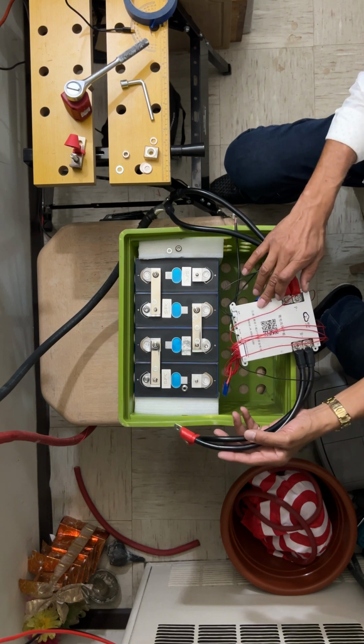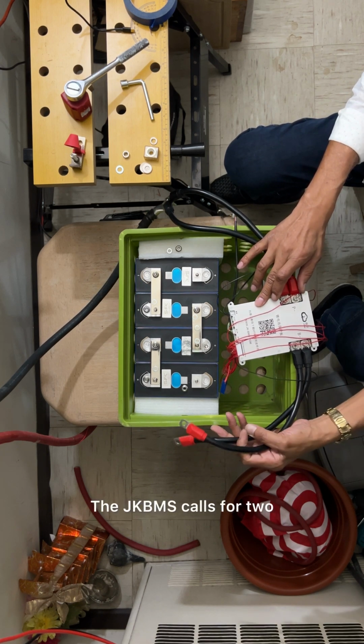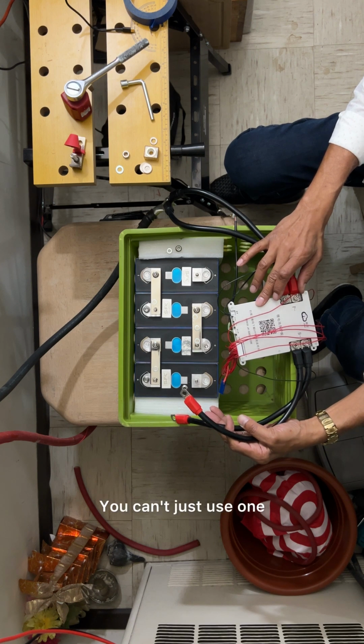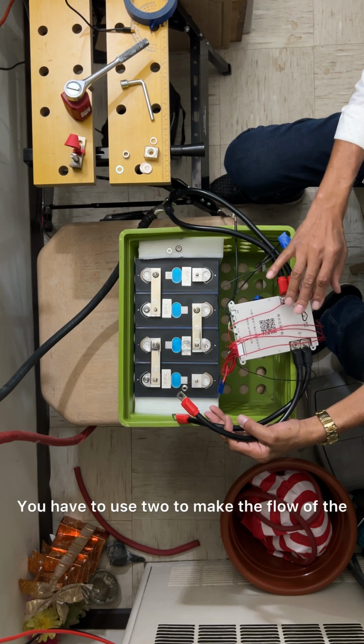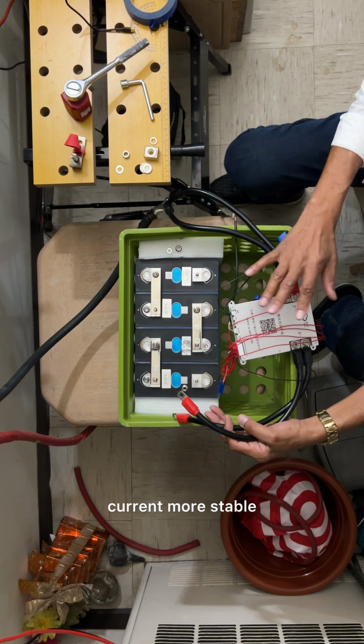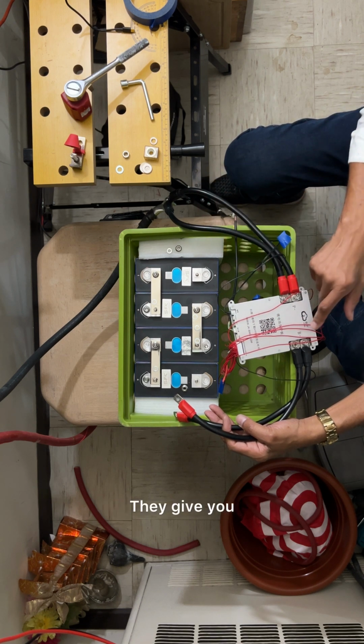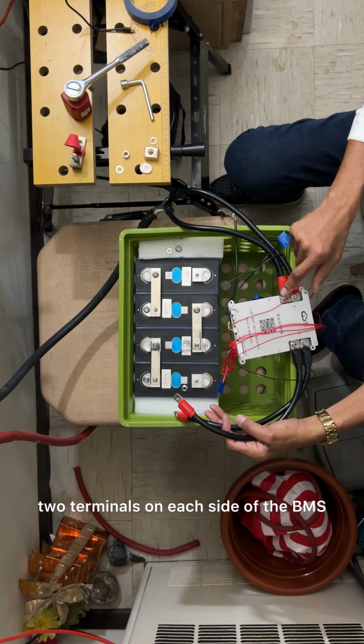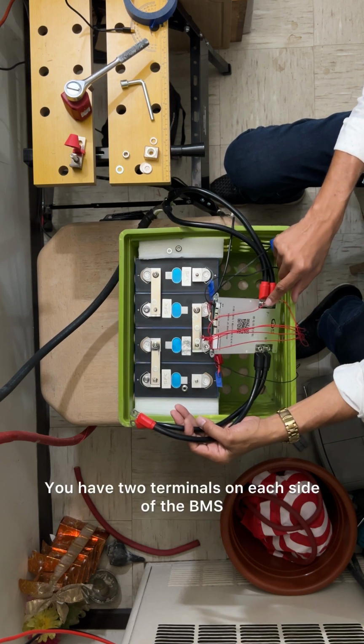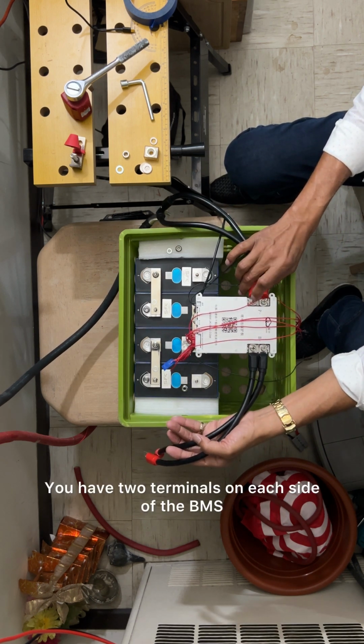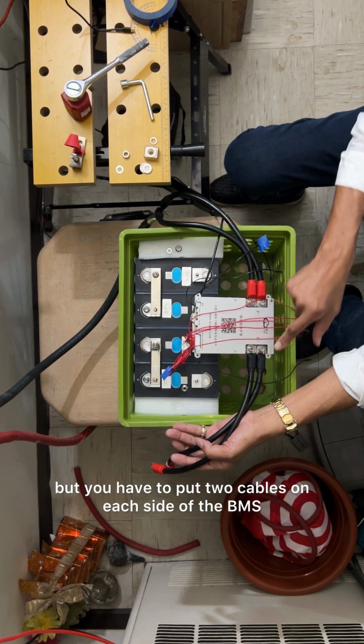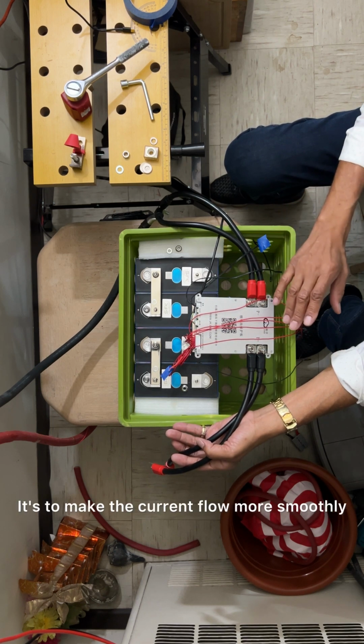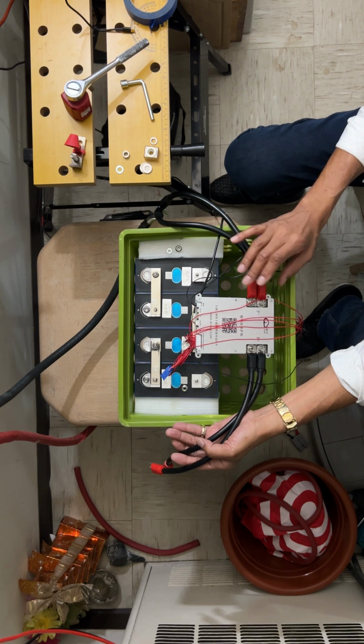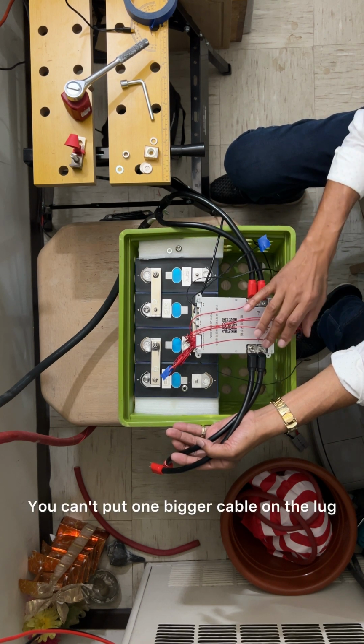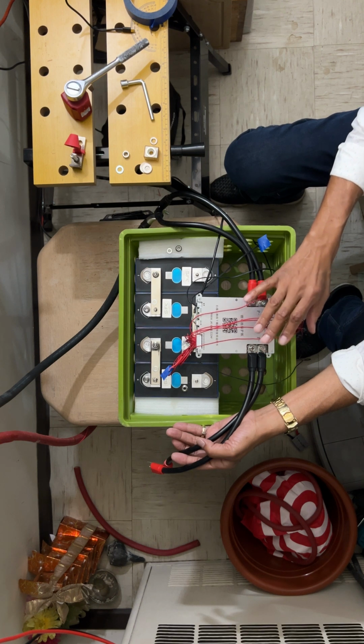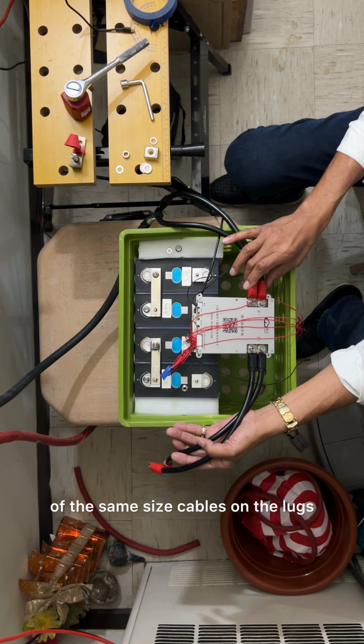The JK BMS calls for 2 cables—you can't just use 1. You have to use 2 to make the current flow more stable. They give you 2 terminals on each side of the BMS for this reason. It has to be done this way; you can't put one bigger cable on the lug, you have to put 2 of the same size cables on the lugs.